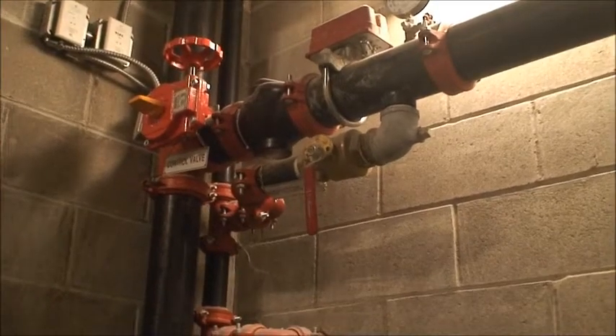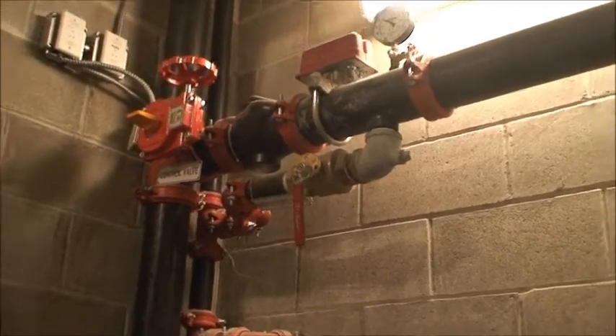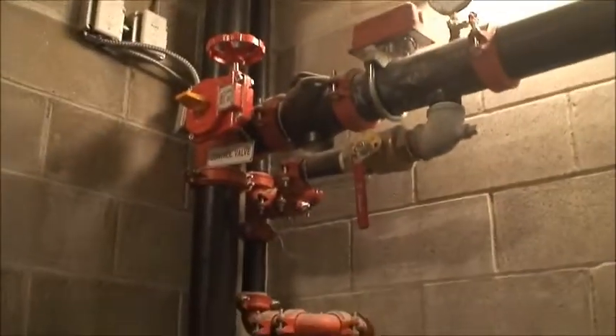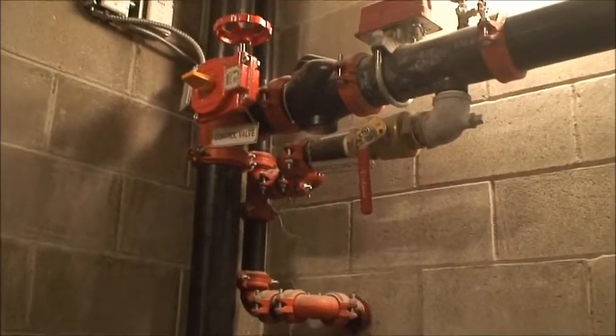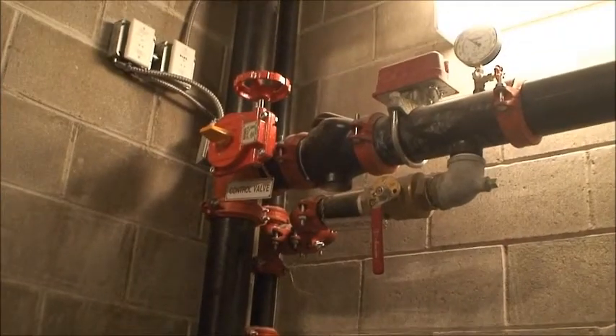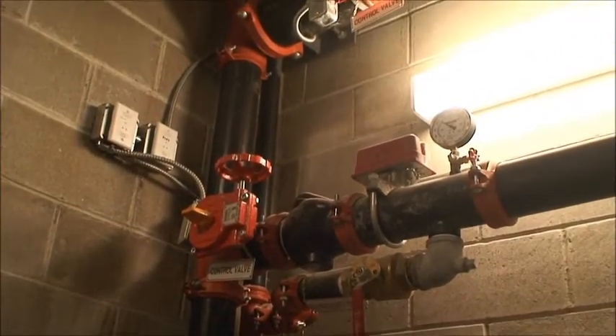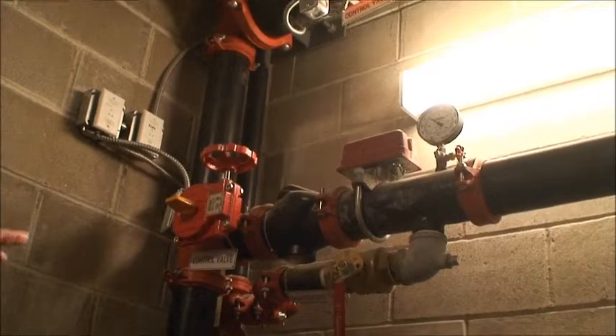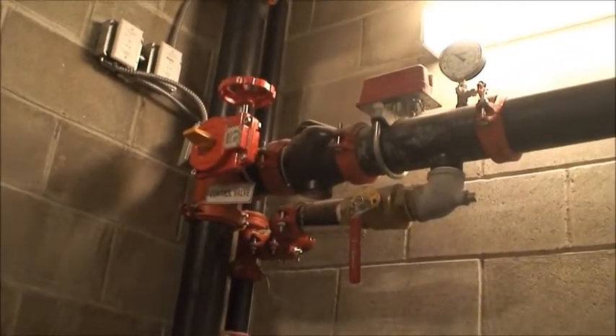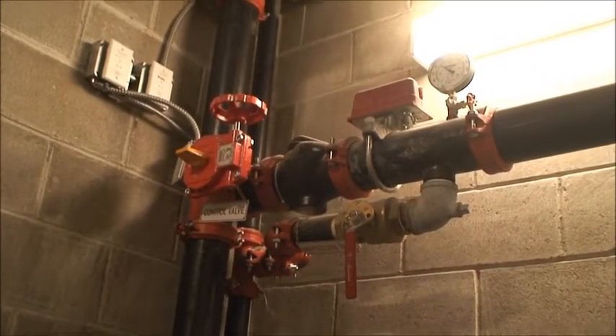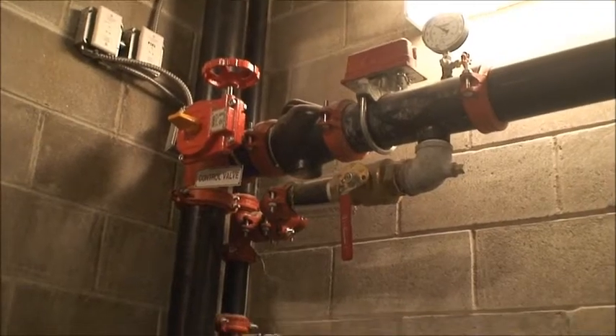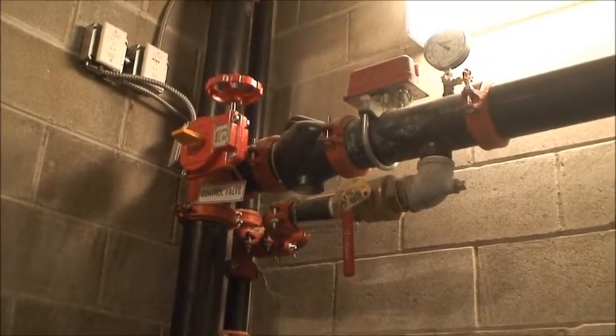That will come out, you'll see that out in the alleyway. There's a spigot, basically. That's how you fill and drain the system. That's how they would simulate a flow test. Okay, they can simulate a flow test. It comes after the flow, so they can open it up and it will drain down, and we can get a flow without actually flowing water on the floor. Okay. All right.